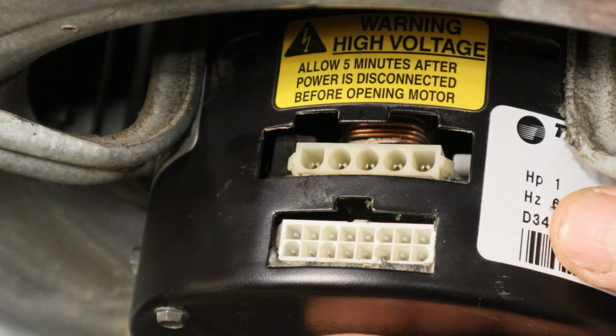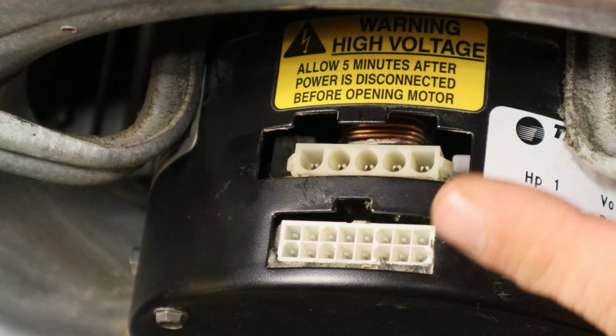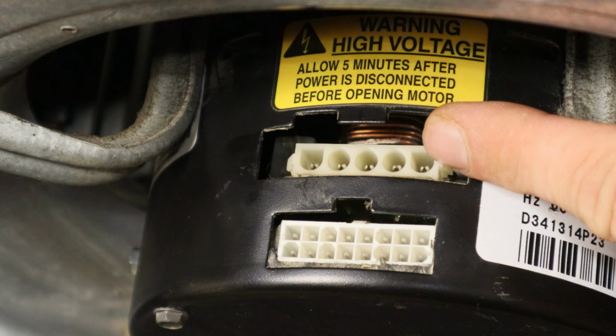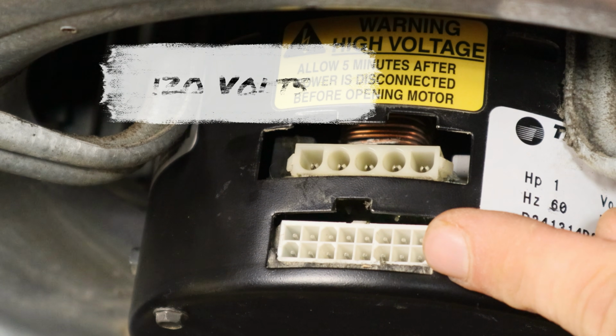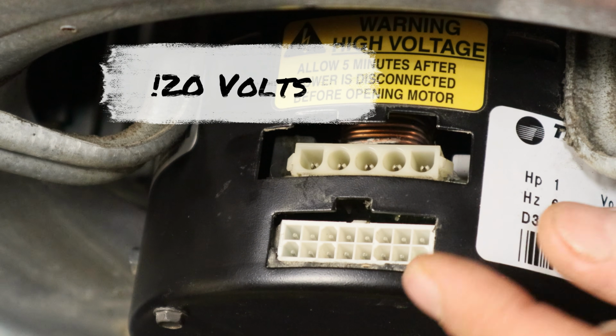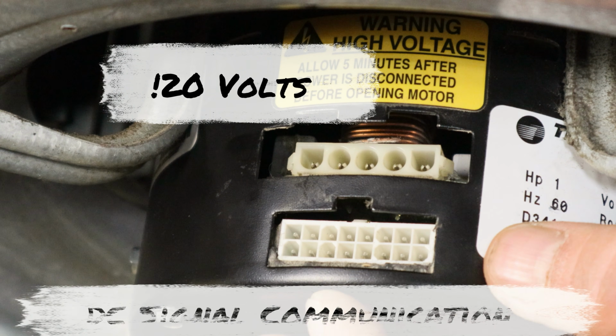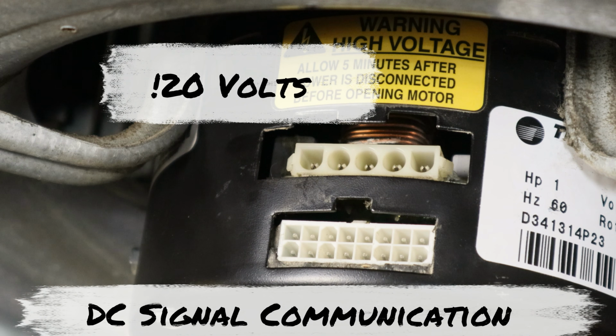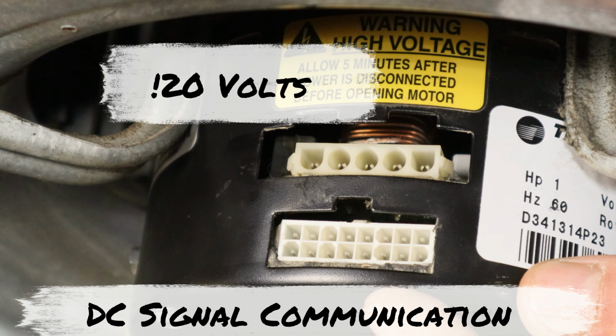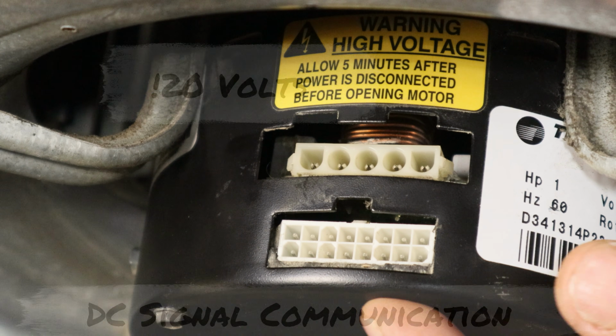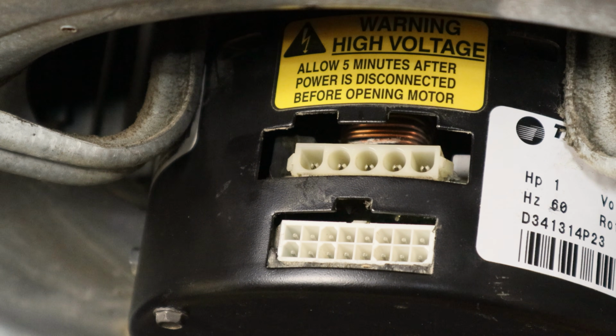Now, all these ECM motors, they have two Molex plug connections. On this one here, this 5-pin connection, this is for our high voltage. These Molex plugs up here, this 16-pin connector, that is all low voltage DC electronic signals. It's communication between the module on the motor itself and the control board. So a lot of data passes back and forth between the control board and the motor module. It's timing, blower speed profiles, synchronization signals, and so forth. So these motors, they always get a constant power supply all the time. So they come on a Molex plug.